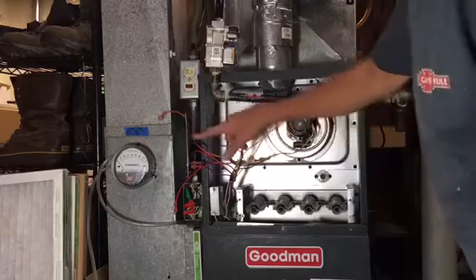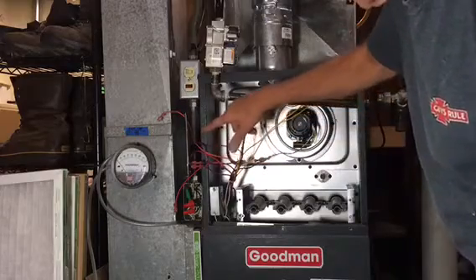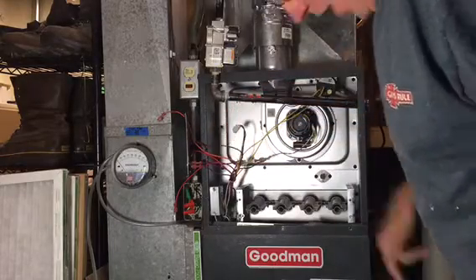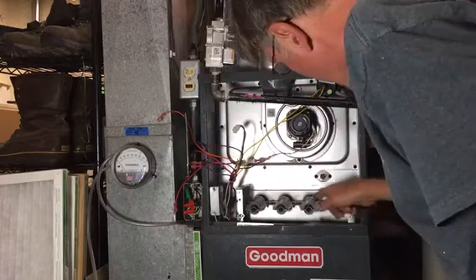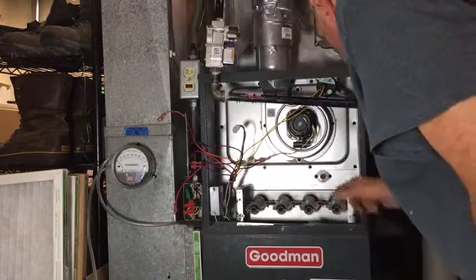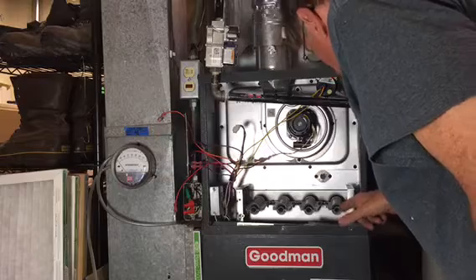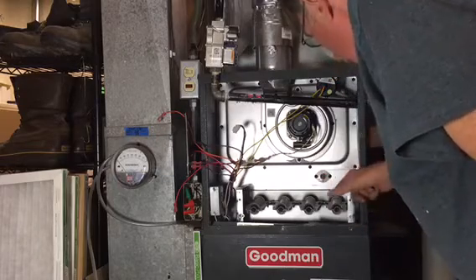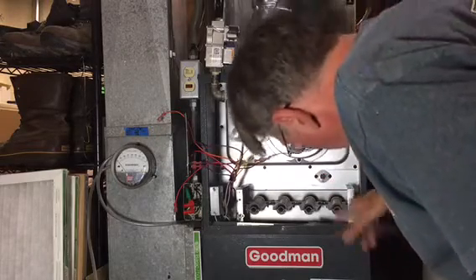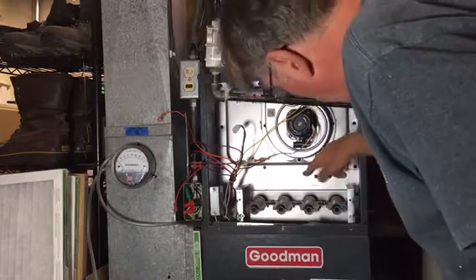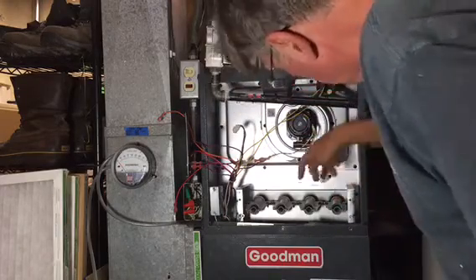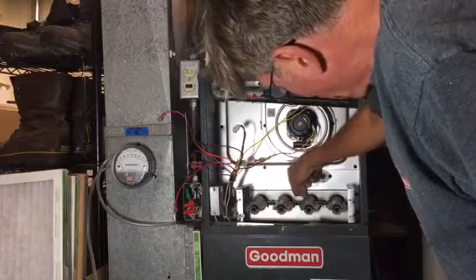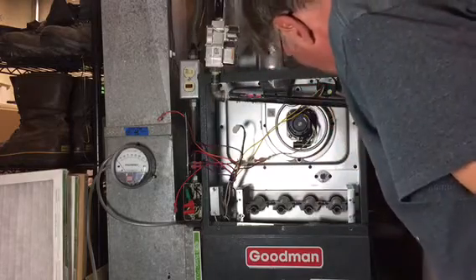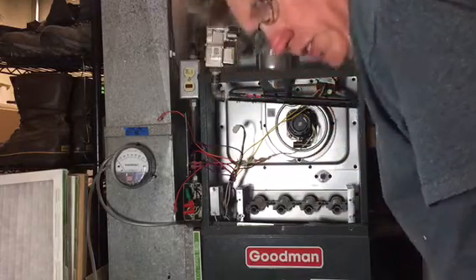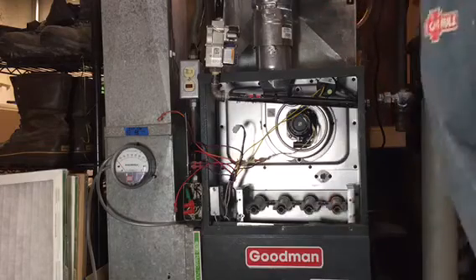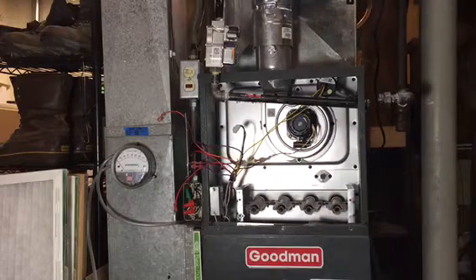Okay, now we've got the burner cover out of the way. I've left some of the wires connected, others I had to pull. And now we've got the individual burners. There's 4, which are called in-shot burners. 2 screws each. We're going to pull those out. Look at the backside, probably clean it. I see cobwebs and things in here. And then the heat exchanger lies where they shoot the gas. So we're going to take a peek in there too with a flashlight and a brush and probably vacuum some. So let's get the burners out. We'll take a little closer look at those later.